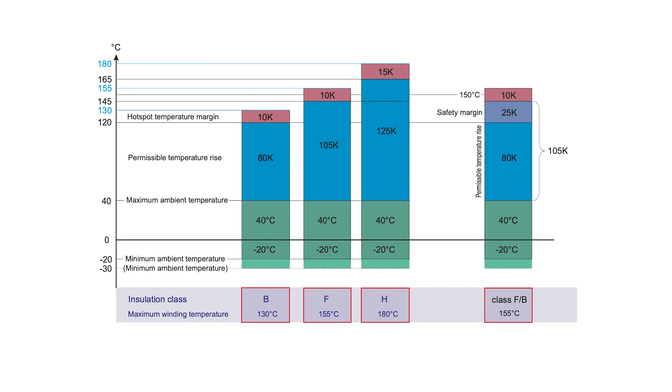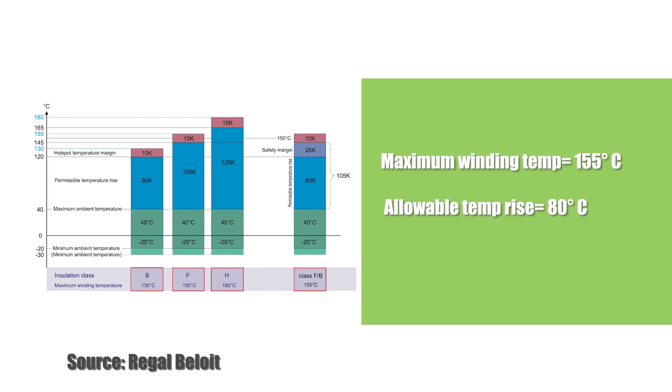Recently, motor manufacturers have begun specifying both the insulation class and the allowable temperature rise, with a rating such as F slash B. The first letter indicates the insulation class, and the second letter indicates the allowable temperature rise. In this case, the maximum winding temperature is 155 degrees C per insulation class F, and the allowable temperature rise is 80 degrees C per insulation class B.